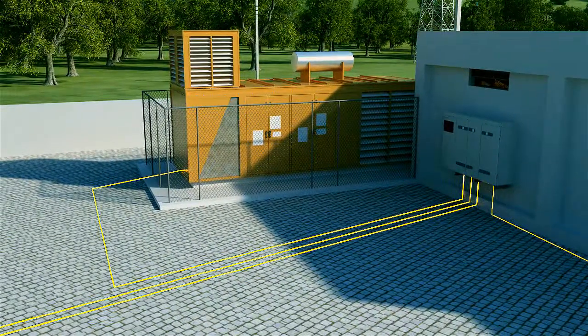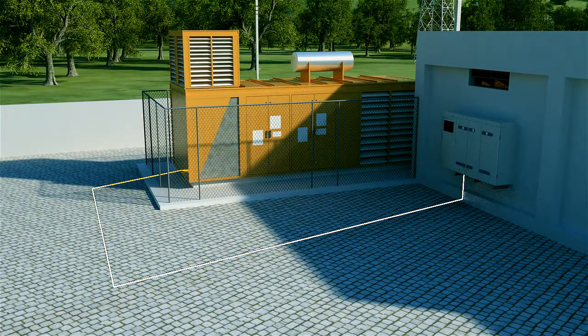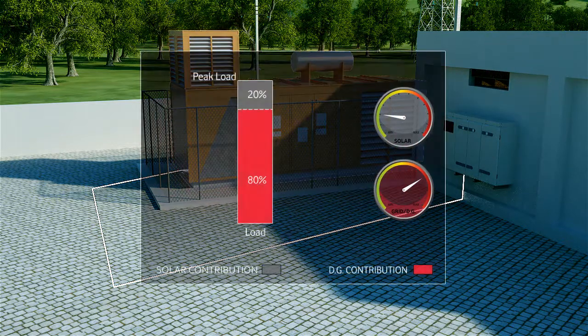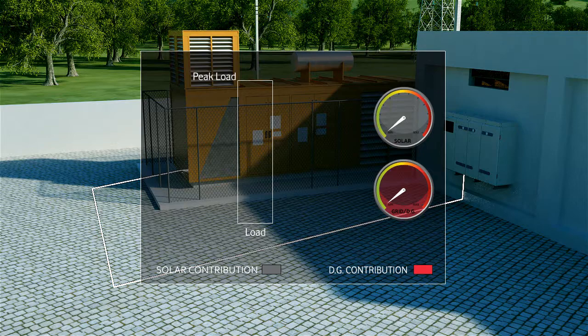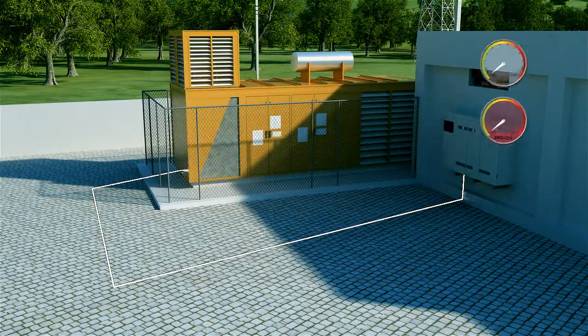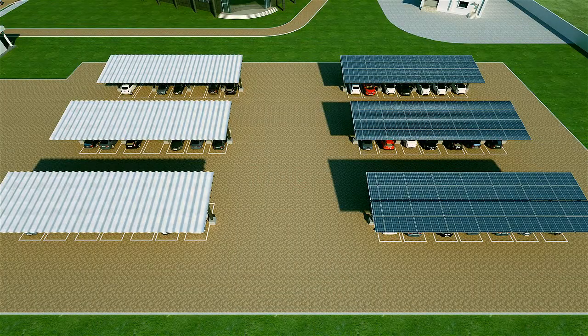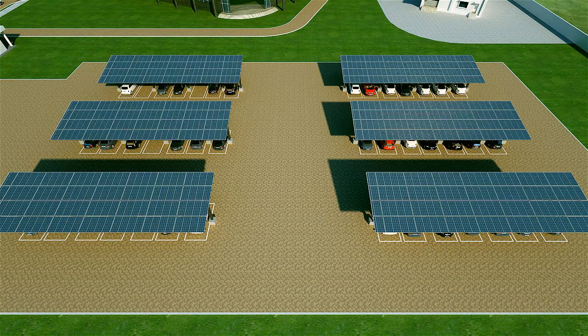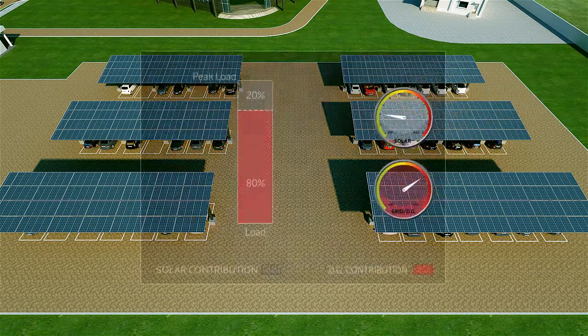If solar produces more power than required by the load, excess solar power will be fed back to the diesel generator, leading to a complete system shutdown. This limits solar power to 20%. MACX, a proprietary product of Mahindra, helps in increasing penetration of solar power with diesel generator to 80%.